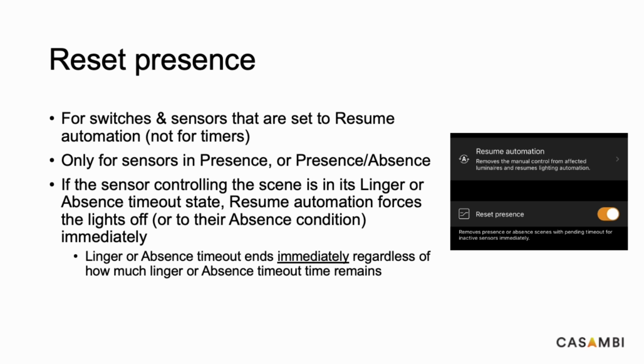First of all, the reset presence option. This is intended for certain niche use cases, so normally should be left disabled. For example, such a case could be if there's a need for an immediate switch off of the lights from a last man out switch.